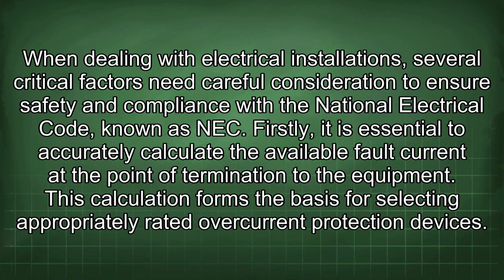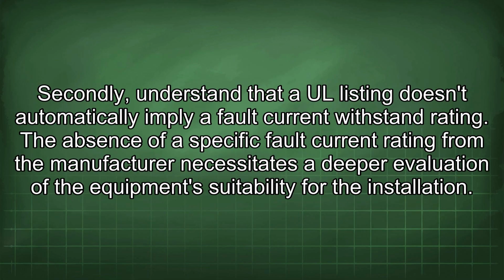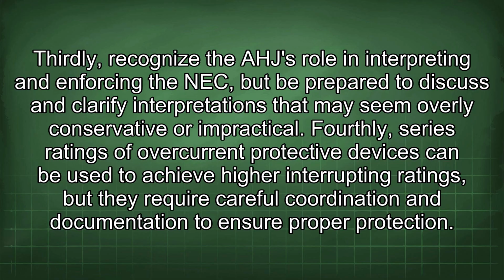When dealing with electrical installations, several critical factors need careful consideration to ensure safety and compliance with the National Electrical Code, known as NEC. Firstly, it is essential to accurately calculate the available fault current at the point of termination to the equipment. This calculation forms the basis for selecting appropriately rated overcurrent protection devices. Secondly, understand that a UL listing doesn't automatically imply a fault current withstand rating. The absence of a specific fault current rating from the manufacturer necessitates a deeper evaluation of the equipment's suitability for the installation. Thirdly, recognize the AHJ role in interpreting and enforcing the NEC, but be prepared to discuss and clarify interpretations that may seem overly conservative or impractical.